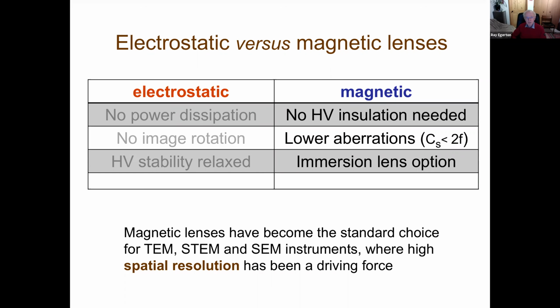Now, you can do the same kind of thing with an electrostatic objective lens, but that means the specimen is sitting within an electrostatic field. And if the specimen is electrically conducting, that will short out the field, distort the field, and you'll lose your focusing. Now, of course, the same thing happens with a magnetic lens if you have a strongly magnetic specimen, ferromagnetic specimen. But ferromagnetic specimens are much less common than conducting specimens. And so I think this is the major reason why magnetic lenses have been used for specimens of all kinds. And it's basically dictated by this requirement for high spatial resolution, small focal length objective lens.